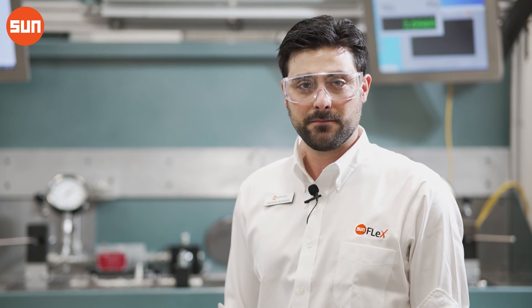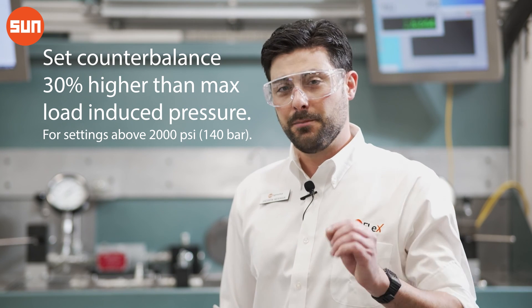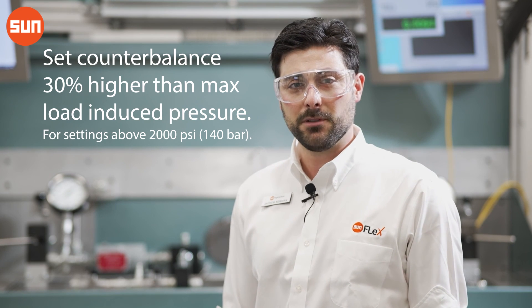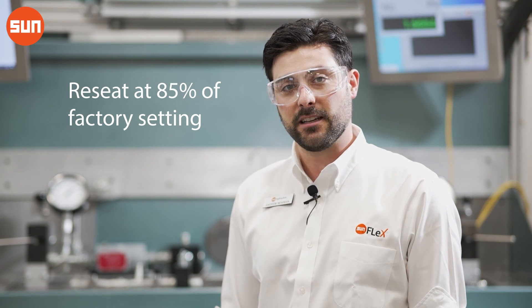And that was how to set a counterbalance valve on a test bay. Sun recommends that the counterbalance valve setting be 30% higher than your maximum load-induced pressure. The valves also reseat at 85% of the factory setting.